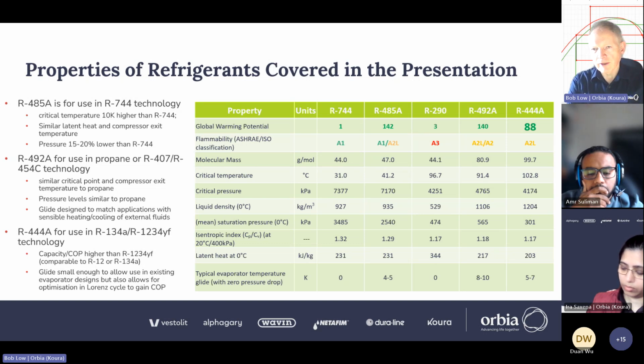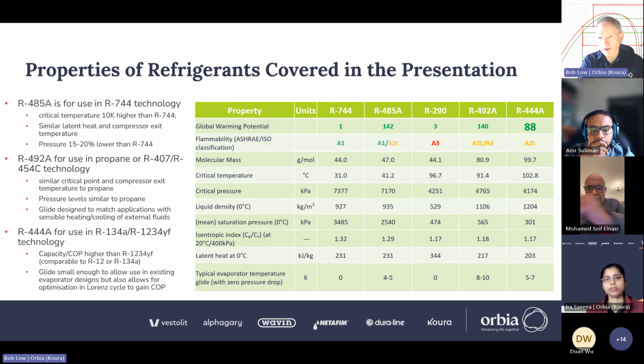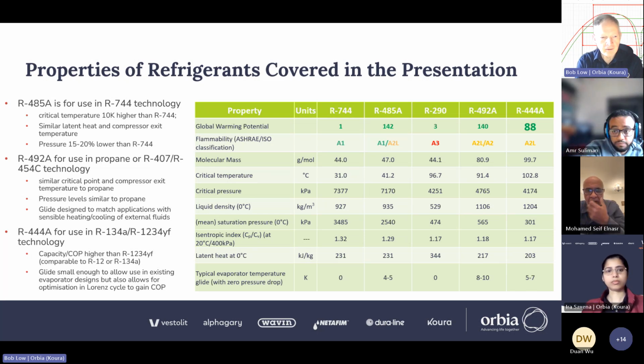492A then is basically the same sort of vapor pressure as propane or the 407 or 454C, 444A type refrigerants. So the critical point is very close to that of propane, for example, it's about 90 C, and the pressure levels are similar to propane. But unlike propane, it's got a glide, and deliberately we designed this refrigerant to have a glide of about 8 degrees, so that it would work well in chiller applications where you're moving heat between fluids, where there's a temperature rise or temperature fall in the source or sink.